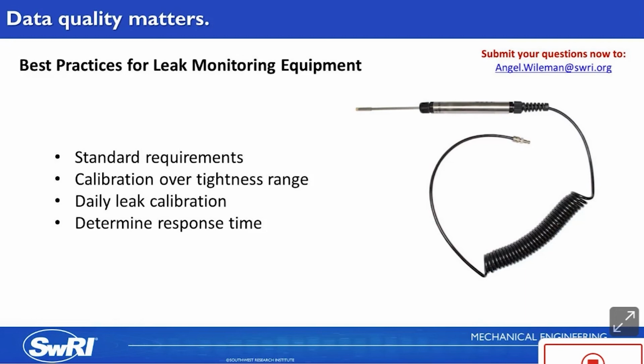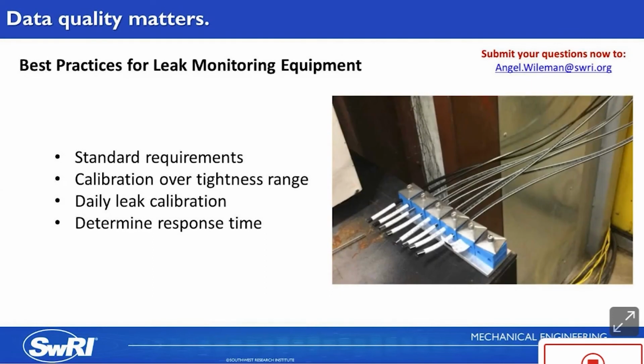response time. And for helium testing, when you're using the bagging or the vacuum method, we like to run our tubing lengths all the way outside of our cell to further isolate operators from the safety hazards. So it's important to consider the length of the tubing run that you have going over to the mass spec probe. The response time must be checked by pulling through the entire length of tubing just as it will be installed during testing.